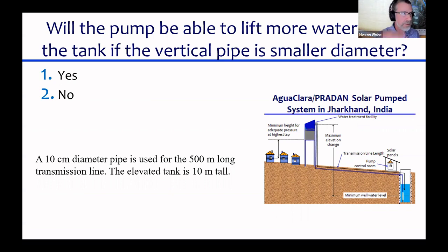That elevation difference between where the pipe discharges and the well is a pressure that the pump has to be able to provide, or lift. And then there's one more source of pressure, and that is head loss.